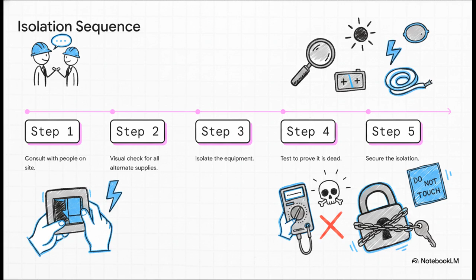I want to zero in on Step 4 for a second, the testing phase. This rigorous 4-step testing loop is your lifeline. First, you test your instrument on a known voltage source to prove the tester actually works. Second, you test between all supply conductors and earth. Third, between all supply conductors. Finally, and this is where people get lazy, you have to retest the instrument on a known voltage source again. Proving your tester didn't break during the process is just as important as the test itself.